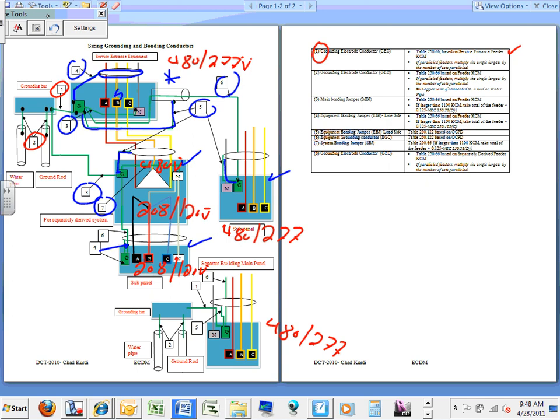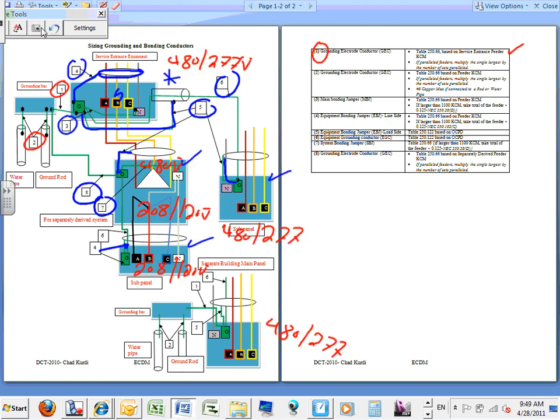Any question, guys, about this before I throw an example for you? Any question? This will cover 99%. The only things that are not covered here, guys, are two things: medium voltage and also DC systems. Other than medium voltage and DC, this will cover every single system: 208/120, 480/277, 240/120, any system that you want. 95% of the systems that we'll be working on are right here, grounding and bonding.